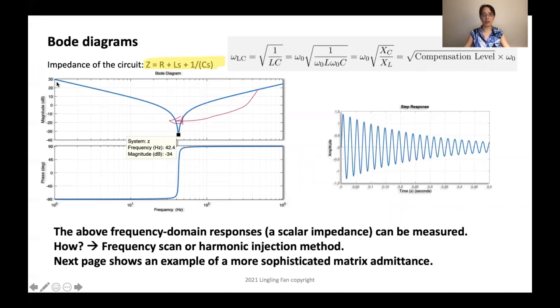So how can we show it in the impedance? We can plot impedance in frequency domain. You can see there's a dip at 42 hertz. So this 42 hertz, in fact, it actually matches this 40 hertz because it means this is very low. So any kind of voltage disturbance, you expect to have a big current at these frequencies. Therefore, we have this thing called sub-synchronous resonance in power grid or RLC resonance. So this impedance is what we want, the frequency domain response. And this is a scalar one. And it can be measured. So how? We can use frequency sweep or harmonic injection method.